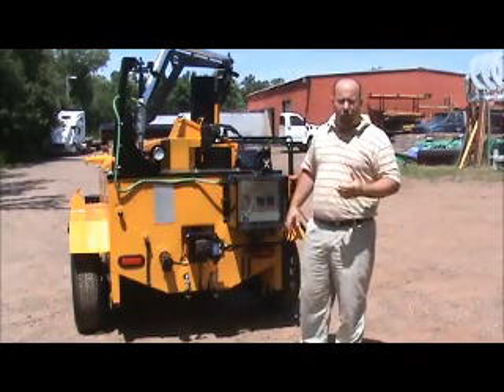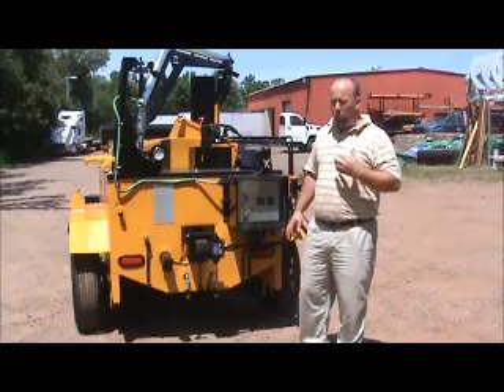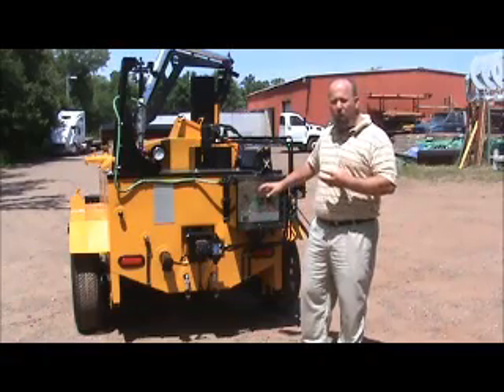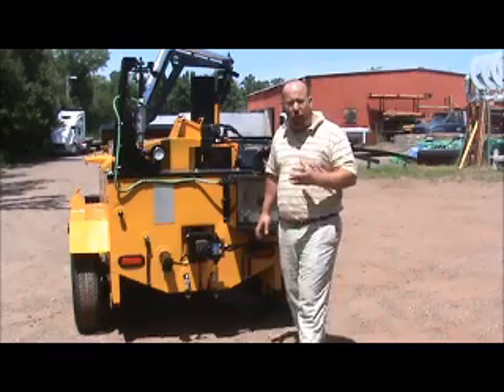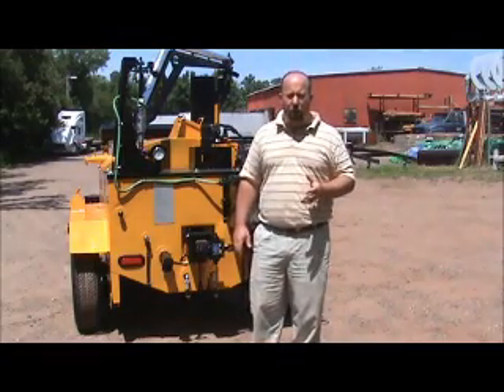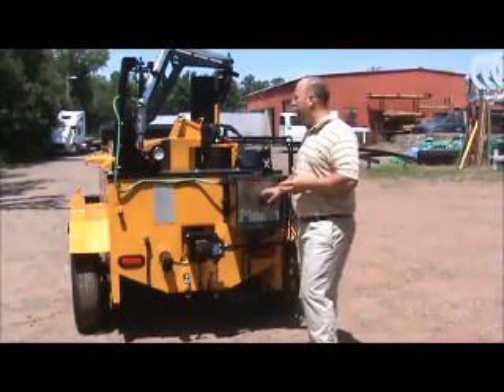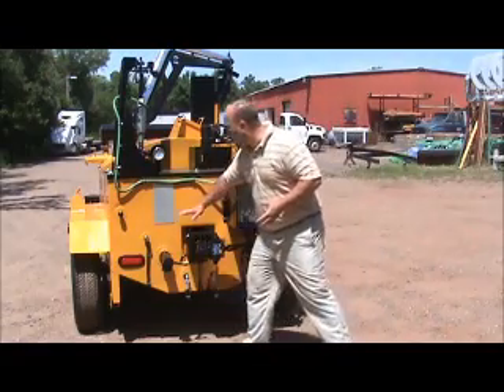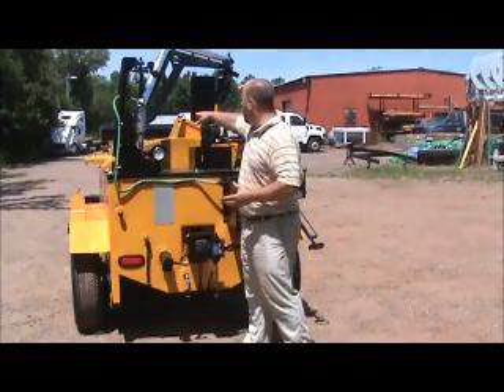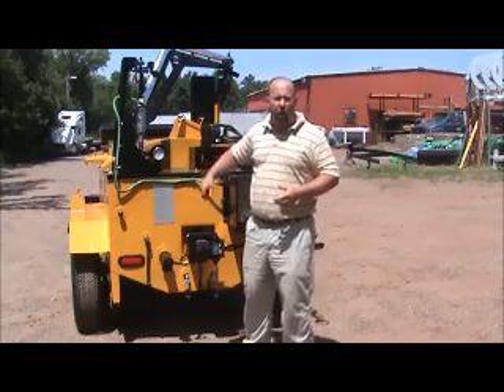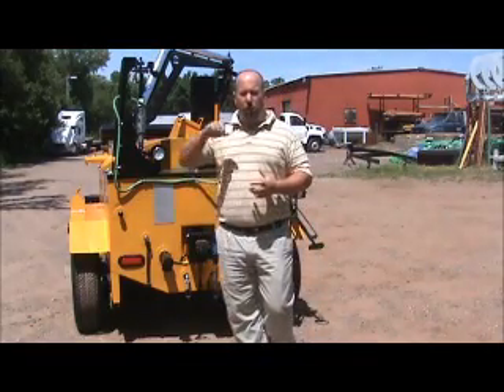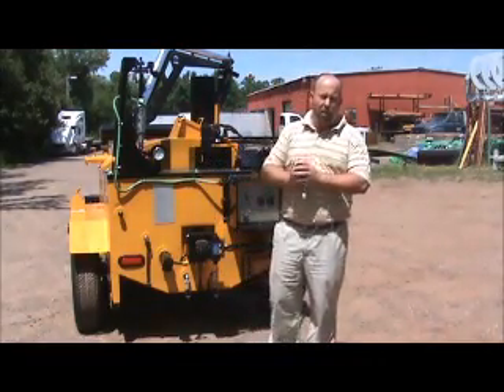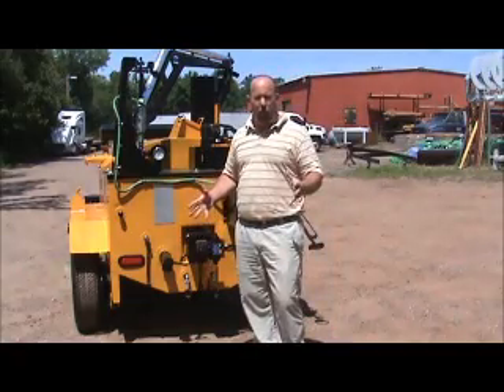It's very important that you don't go over that. If you're working and it's real cold and real windy, you can run that a little higher, at 450, but never over 475. If you heat this thing up to 500 degrees, your oil is actually going to expand into the tank, into the overflow tank, and then spit out on the ground. If it's over 500 degrees, once it comes out that overflow and hits the air, it's actually going to catch on fire because it'll combust.